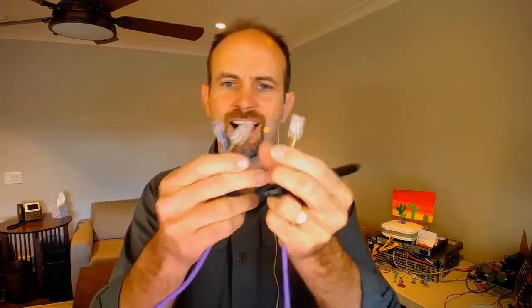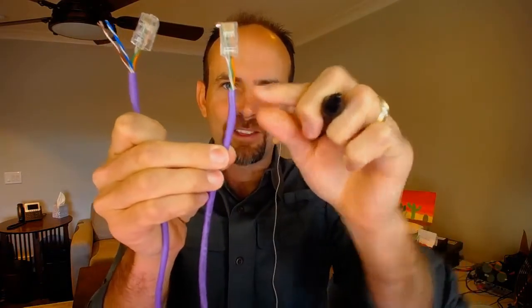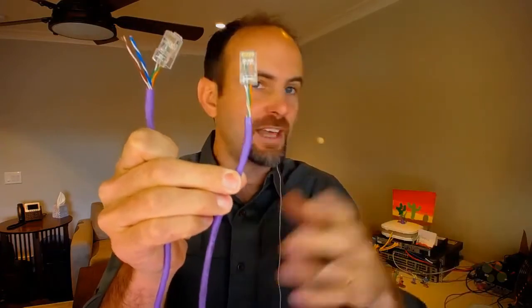And so, if it becomes loose or disconnected, you can end up with a bad cable. Now, typically, and one of the things that you should know, and let me explain why I've got this messed up cable. By the way, I hate it when people do this, where you've got the shielding and it ends, and then you've got this nice little stretch of the individual wires. That is definitely case in point of a cable that will likely go bad.